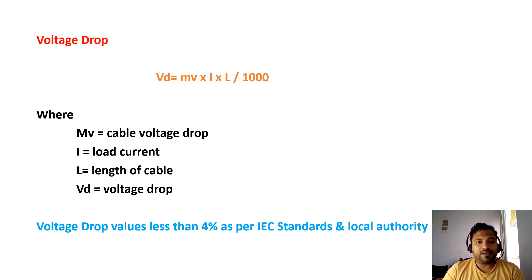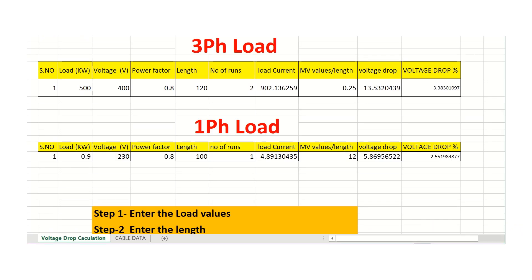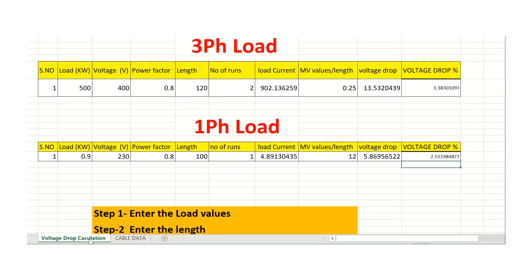Let's go back to the Excel sheet. This Excel sheet has two pages: one is the voltage drop calculation, and the second is the cable data sheet. With the help of this Excel sheet, we can determine three things: the size of cable for a particular load, how many runs of cables are required, and finally, how much voltage drop is obtained.